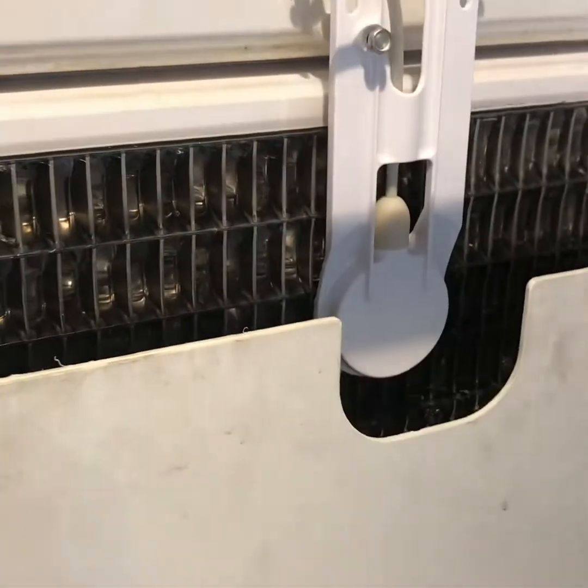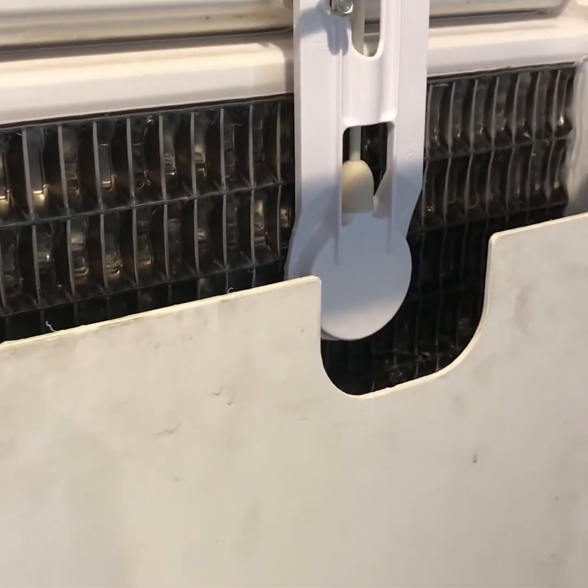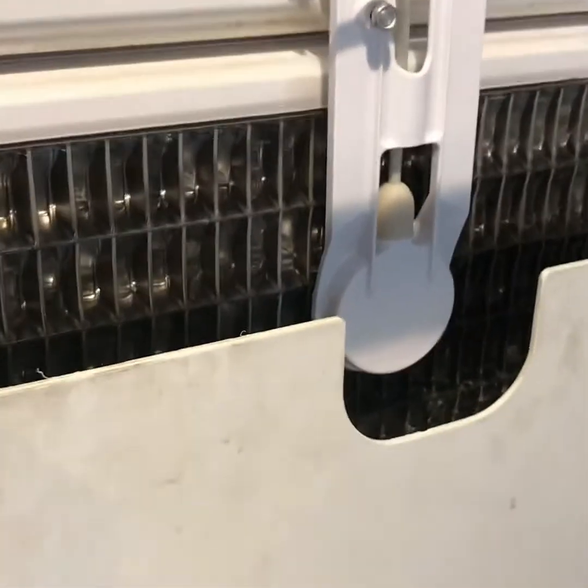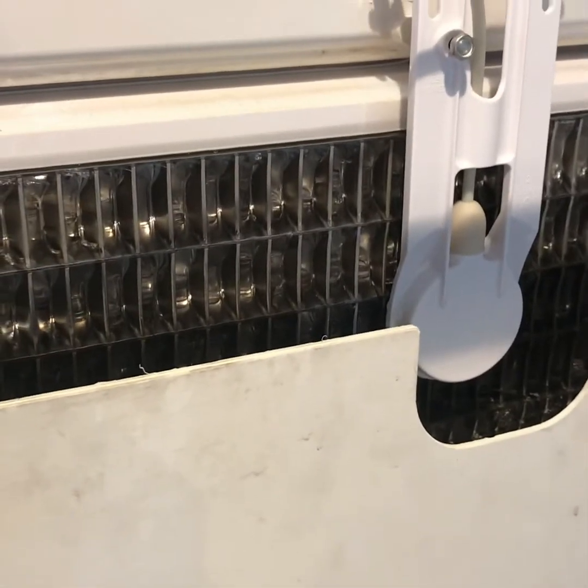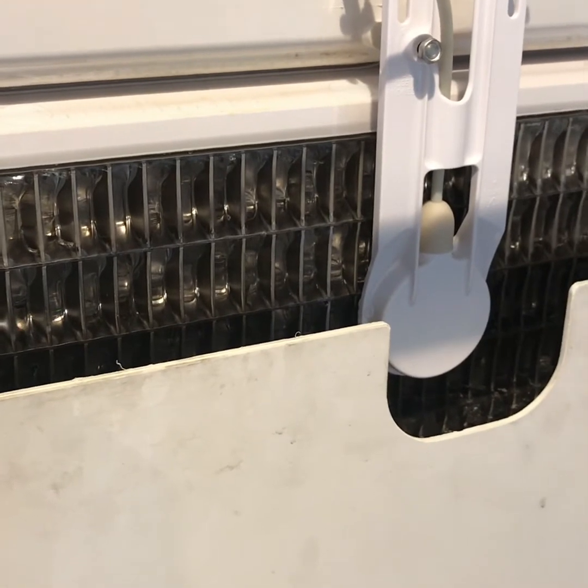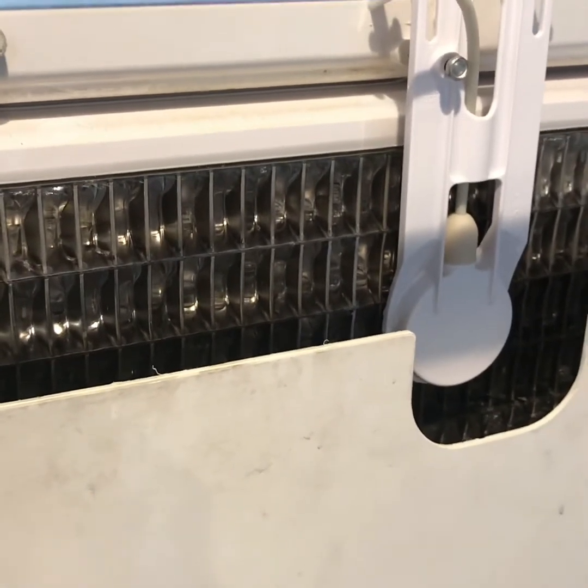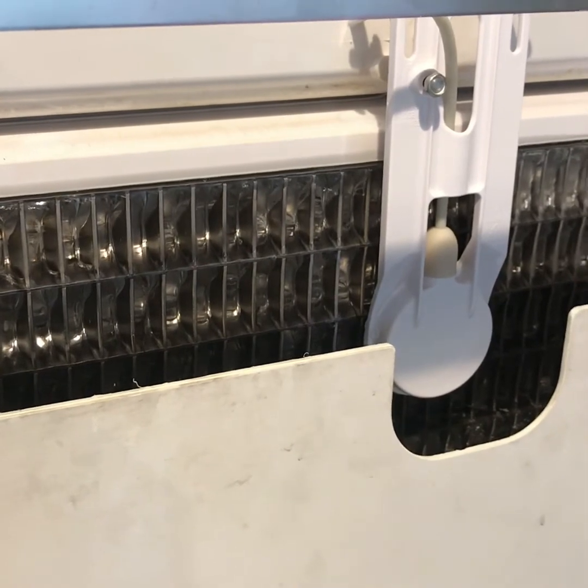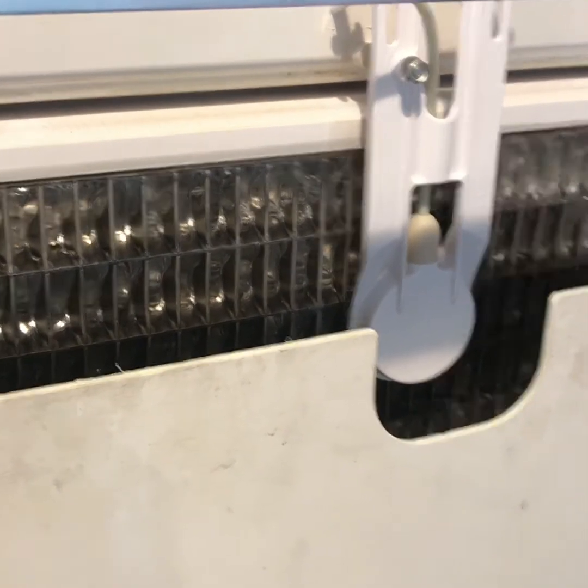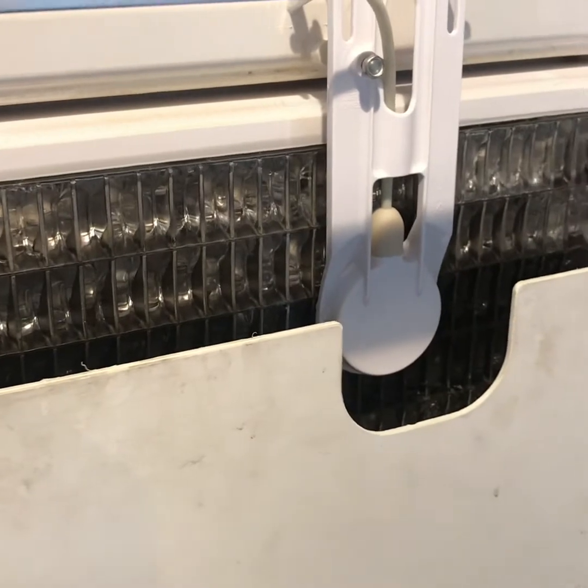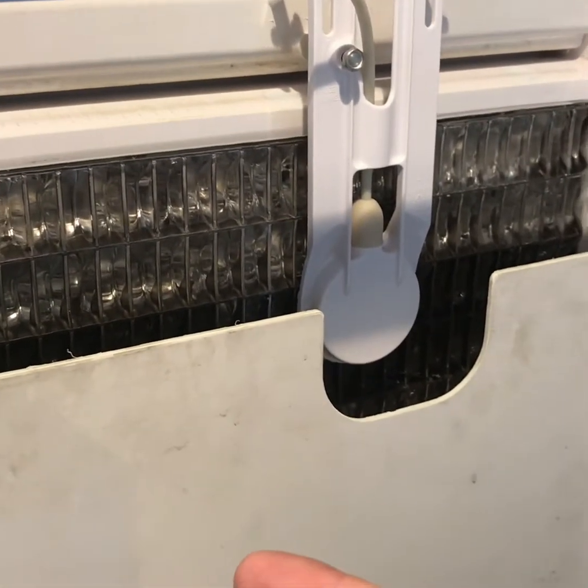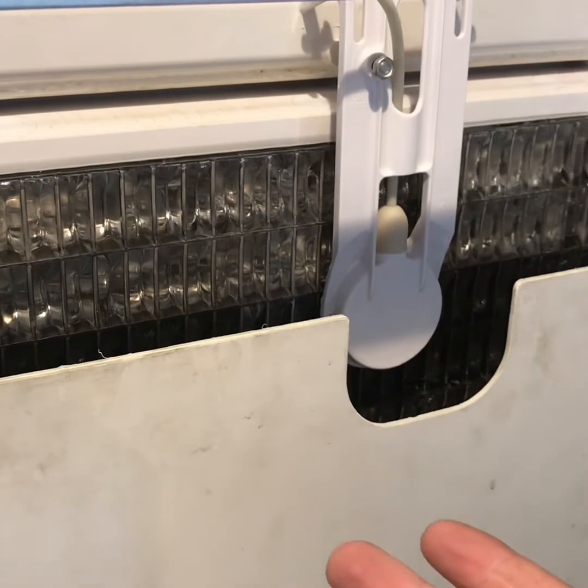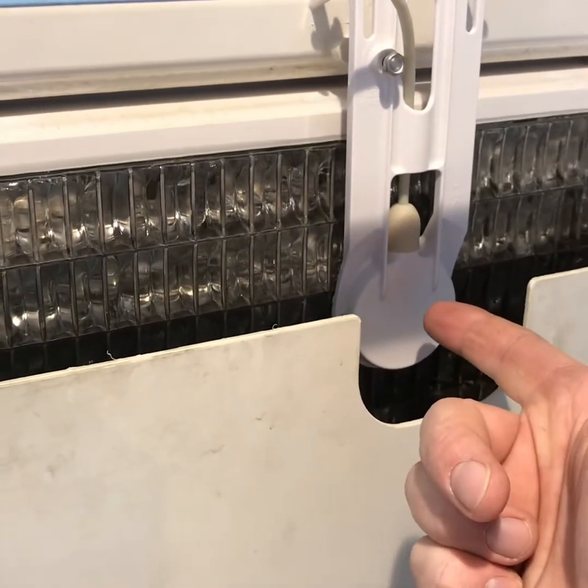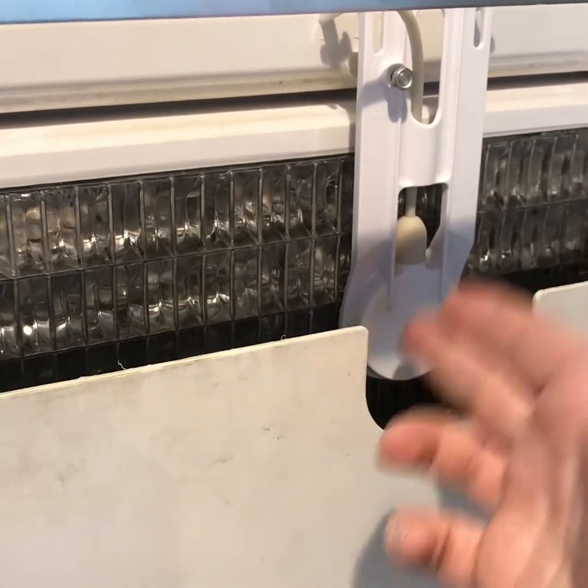I had to adjust it a little bit again with just the screw on there. A lot of times with troubleshooting an ice machine, it's just patience -- sitting there and watching it, seeing what it does and what it's not doing, and then correcting the problem. It was building a big chunk of ice, so we knew it was either not falling off or not going into a harvest, and it was obviously not going into a harvest because this wasn't sensing it. Now we know the difference and how to check and test to see if it's this or the control board.